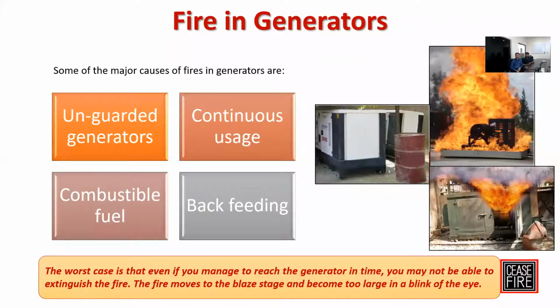They have inbuilt combustible fuel inside. Sometimes backfeeding also happens - malfunctioning of switch gears - through which power coming from outside goes inside the generator and causes a fire. These are the major causes, and again, I'm repeating that you cannot extinguish generator fires using any manual method. That is the most difficult part of fires in generators.